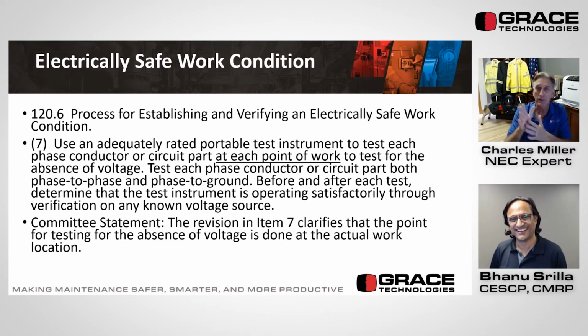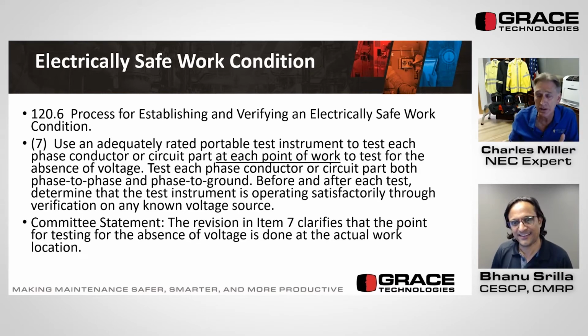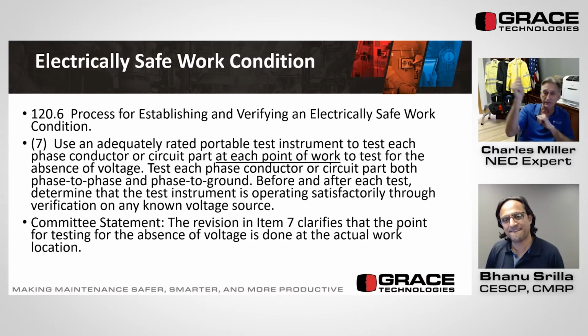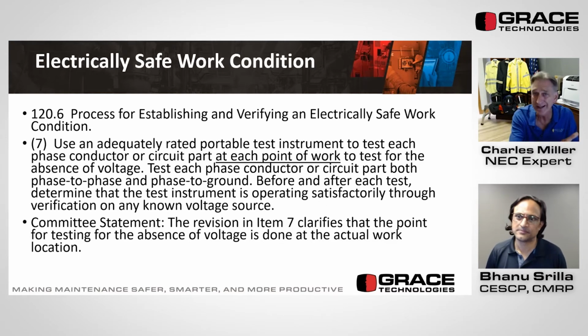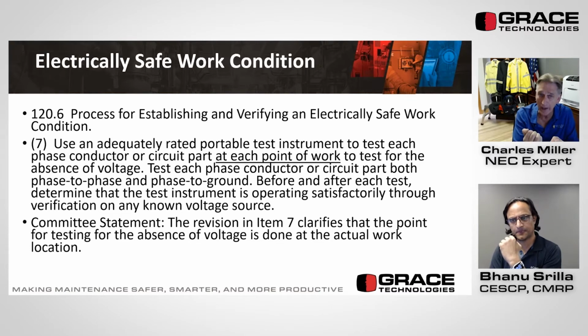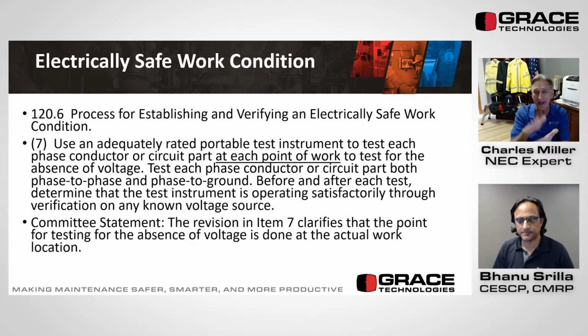So we have power coming to a building. The utility company says the building's going to be demolished. They come out, cut it loose, it is totally gone. Right now, the way it is, a qualified person could go out, and where the power comes in, maybe at the service disconnecting means, they could open it up. They have to be suited up, of course. They could open it up, testing for the absence of voltage at the first point where it comes in.